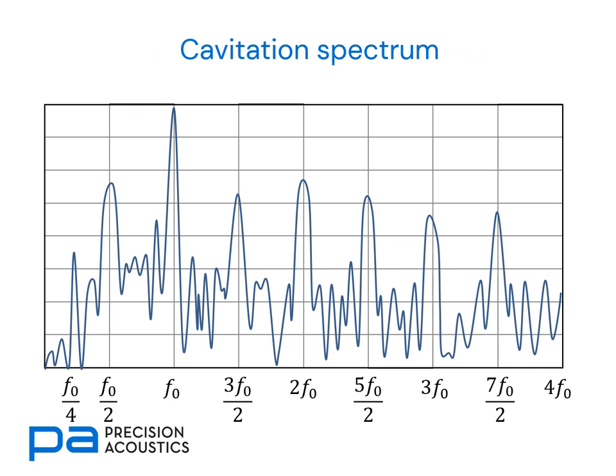We'll have seen from that previous tutorial that cavitation spectra can sometimes be very complex. Here we can see multiple harmonics, sub-harmonics and ultra-harmonics of the fundamental F0. What's also important to note is the difference in amplitudes — quite often the fundamental can be some 40 dB larger in amplitude than the next nearest spectral component.